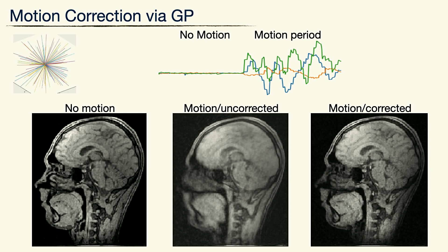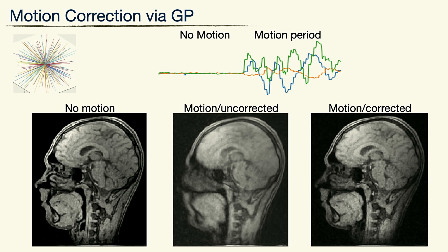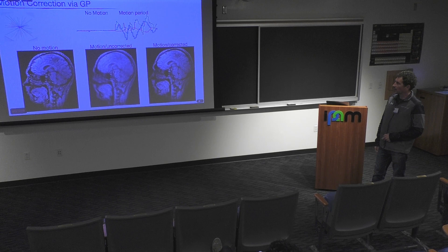Then during high-resolution acquisition, we collect BPT simultaneously, use the trained coefficients to estimate rotation and translation, and correct the high-frequency data. Translation is a linear phase and rotation is a rotation in the Fourier domain, so correction is straightforward. The results show that without motion, you get a clean brain image. With uncorrected motion, you get blurring and streaking artifacts. After applying BPT-based correction, the structure becomes visible again — not quite as perfect as the no-motion case, but much, much nicer and diagnostically useful versus non-diagnostic.